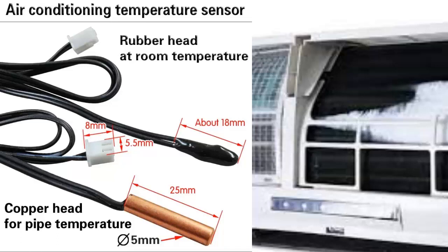7. In case there are issues with temperature sensors, they can lead to evaporator freezing and reduced airflow. In this case, the temperature sensors should be checked.